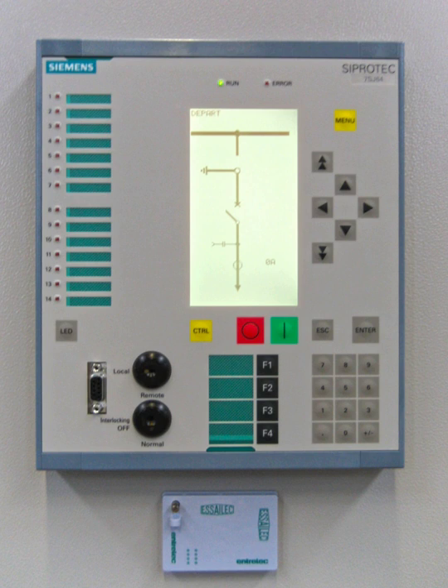Switchgear is a combination of electrical disconnect switches, fuses or circuit breakers used to control, protect and isolate electrical equipment. Switches are safe to open under normal load current. Some switches are not safe to operate under normal or abnormal conditions, while protective devices are safe to open under fault current. Very important equipment may have completely redundant and independent protective systems, while a minor branch distribution line may have very simple low-cost protection.